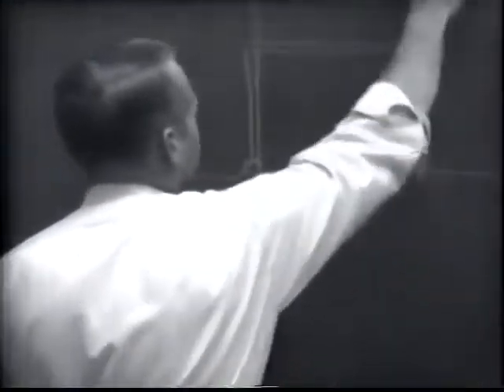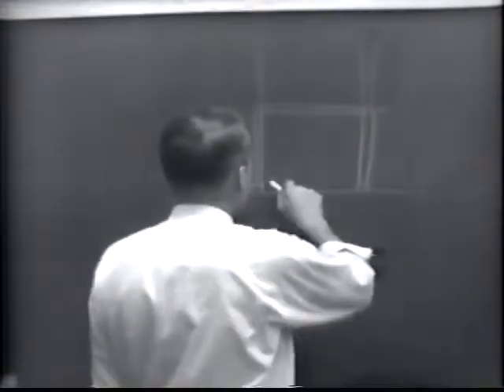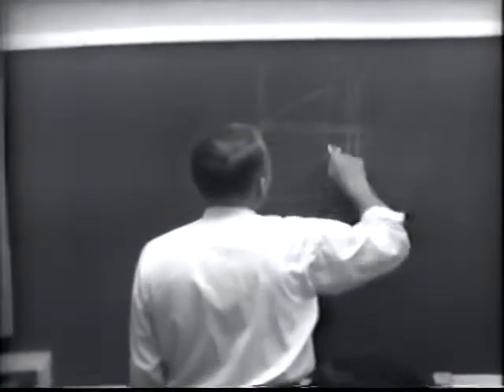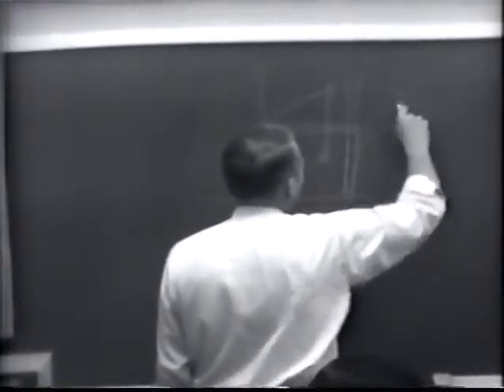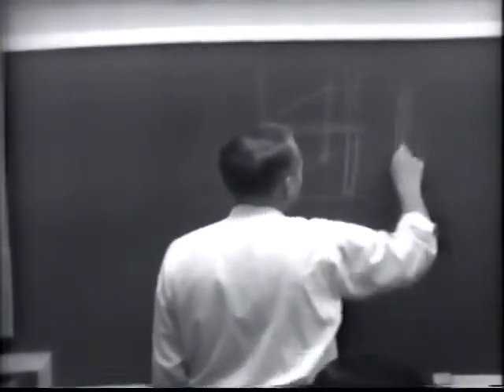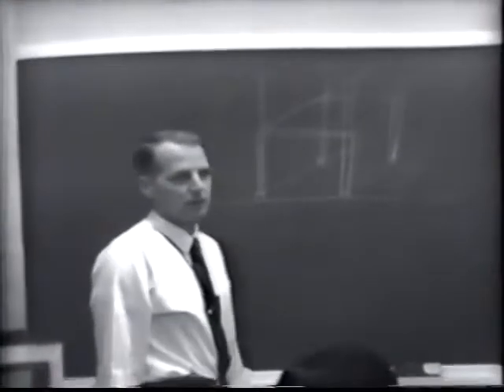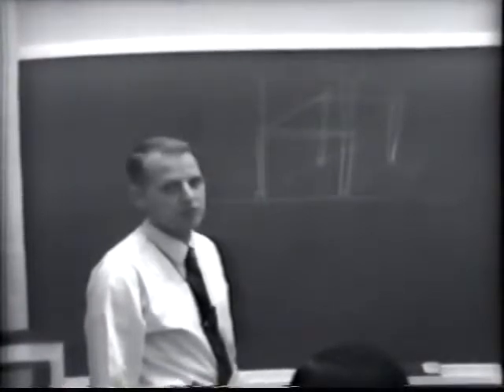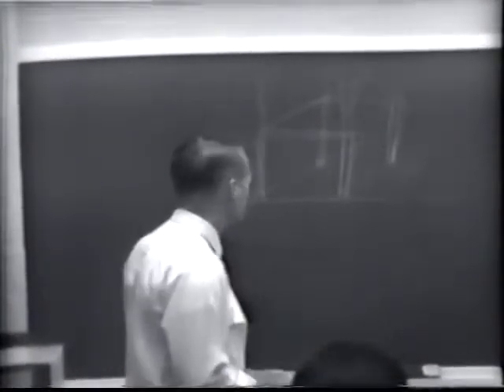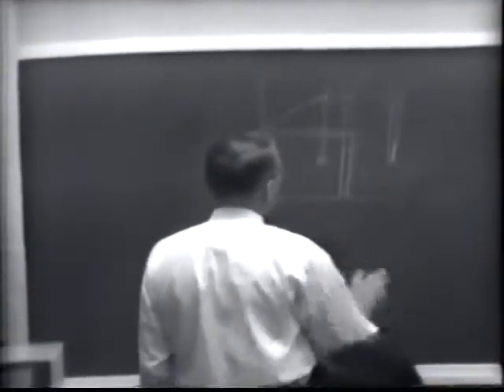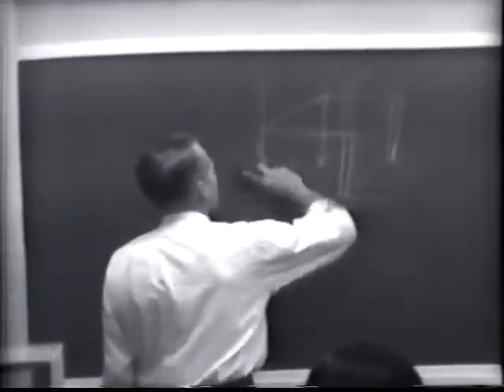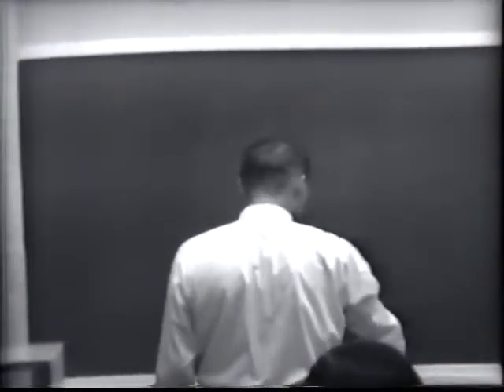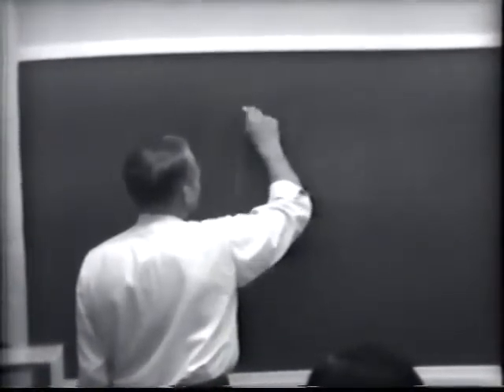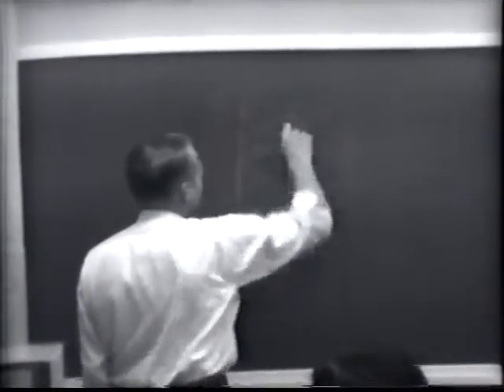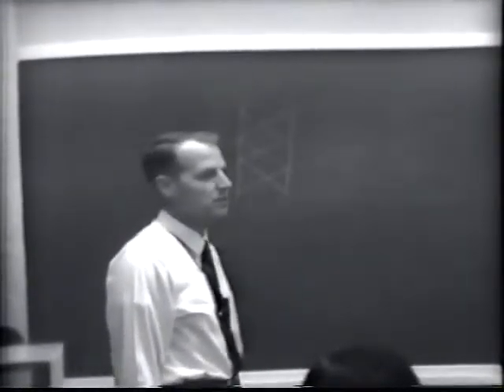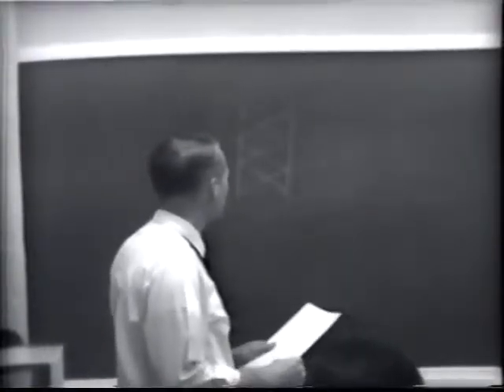And then we'd have others coming up here, and looking at it in a perspective, this would continue on down this direction. We'd have another bay down here, and that would be laced across to this bay here, and then continuing on that way. This would be the type of structure that's quite common in our 69 kV substations up until the past few years, this continuous beam. Now we have one example of this continuous type of substation structure, the laced framework. We have this same general arrangement, but each of the columns is composed of an angle with a lacing back and forth, something like that. Substation 58 in Bettendorf has this arrangement, and it does present a little more bulkier appearance.